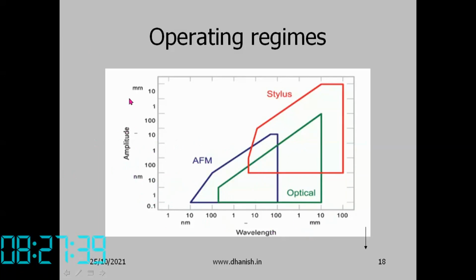Whereas for large amplitudes, say 10 mm, to wavelength of 100 mm, suppose extreme conditions, the Stylus instrument is possible. Up to say 10 microns wavelength and amplitude again 10 microns, this sort of range is possible in the Stylus type instrument. And optical type, low amplitude, no problem. The wavelength is somewhere in between. For large range surface roughness, etc., the optical instrument, that is the interferometer type or focus variation type instrument, is not suitable. Focus variation can also be considered an optical instrument because it has a camera and tries to focus. So these are the operating ranges of the different types of instruments.